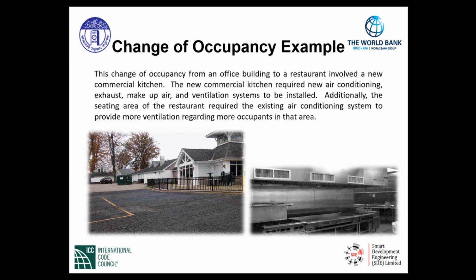Additionally, the seating area of the restaurant required the existing air conditioning system to provide more ventilation, regarding more occupants in that area. This is a mechanical ventilation system that brings in outside air. It was analyzed and modified to introduce more outside air in liters per second and was calculated for the occupant density given this new change of occupancy. And further along, we will have an example coming up of a ventilation requirement for mechanical ventilation, and we will go through a step-by-step procedure and show you how to calculate minimum ventilation rates for outside air to be brought in mechanically into our buildings.